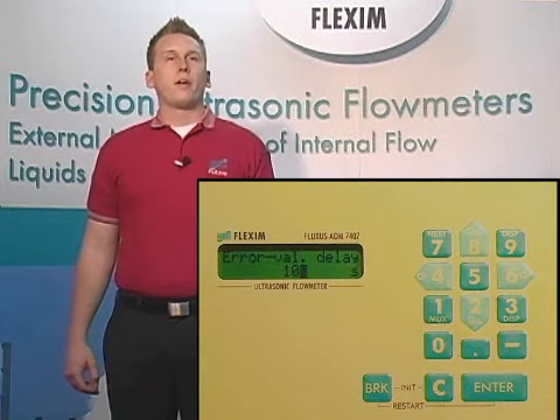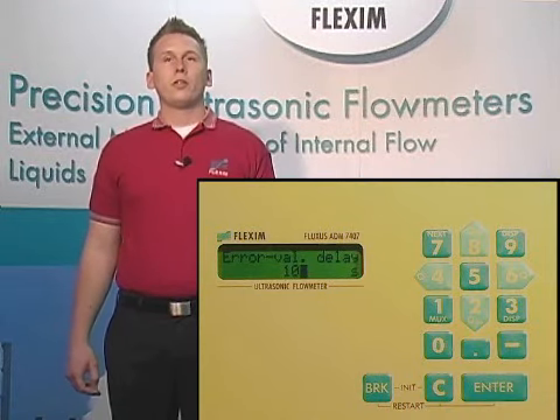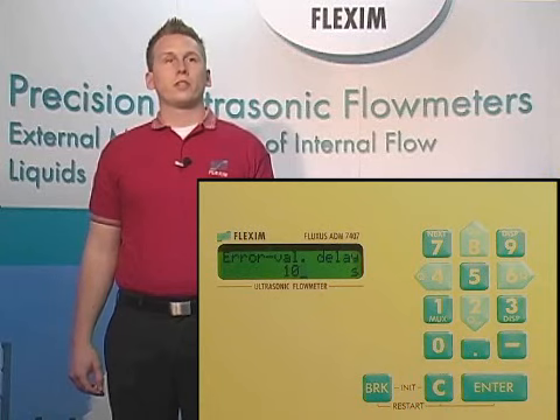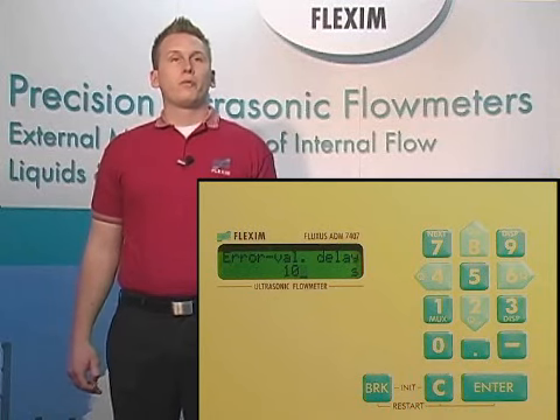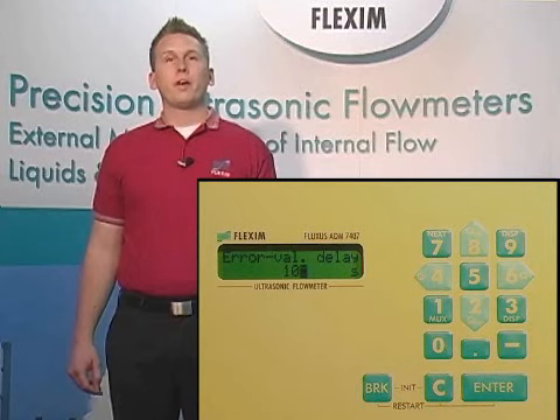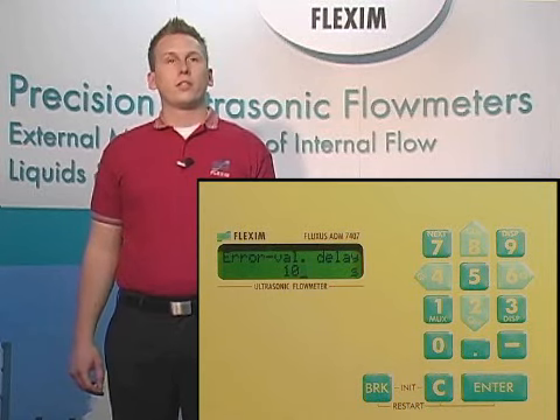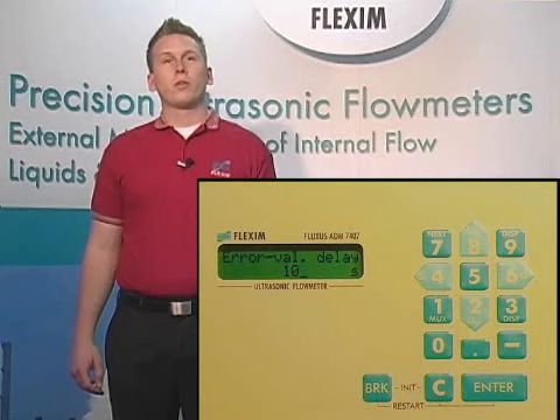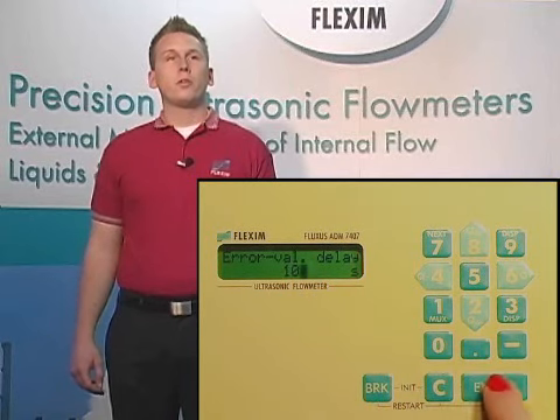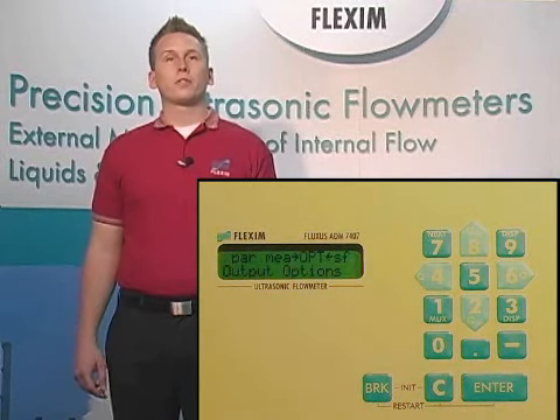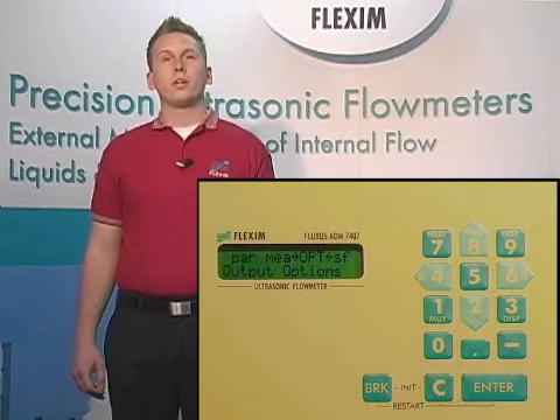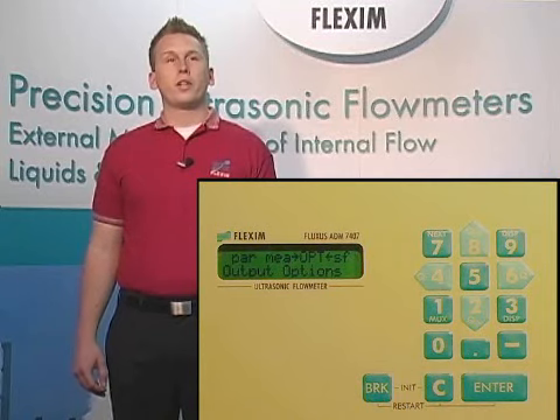And to enter a value for error delay. This will determine how long your meter will wait before sending out an error signal to your PLC. Before, in special functions, we specify the value for our error signal. This is how long the meter will wait in an error condition, such as an empty pipe, or very high solids or entrained gas before giving you an error. I'm going to choose 10 seconds, but good values for this are entirely determined by you. My preference is to probably stay between 10 and 30 seconds in general. Now that we're fully through the output options menu, we're done.